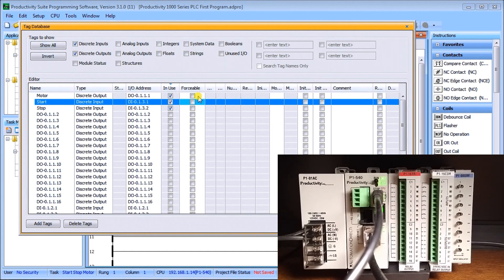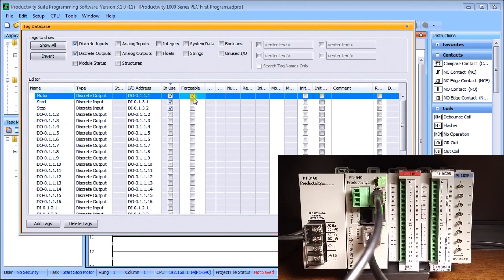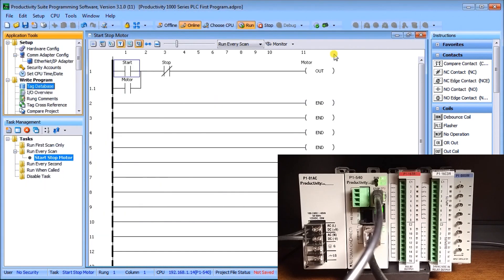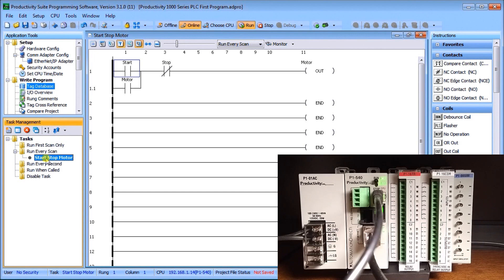When online, we'll be able to force contacts on and off through the Productivity Suite programming software. We'll mark Motor and Start as forcible and leave Stop as unforceable. Closing the Tag Database, you'll notice the program now shows those names and looks more readable. The second thing we're going to look at is Tasks, found in the Task Management panel. Here we have our 'Start Stop Motor' task running every scan.